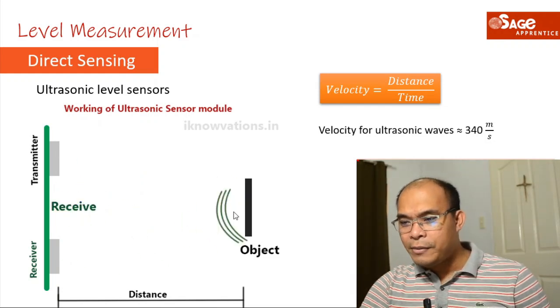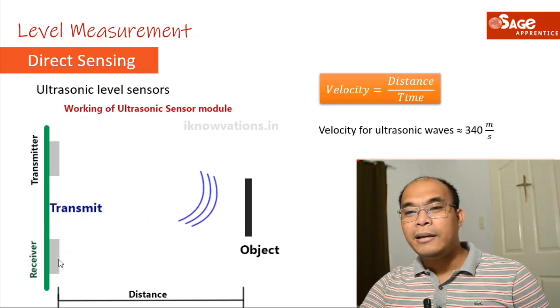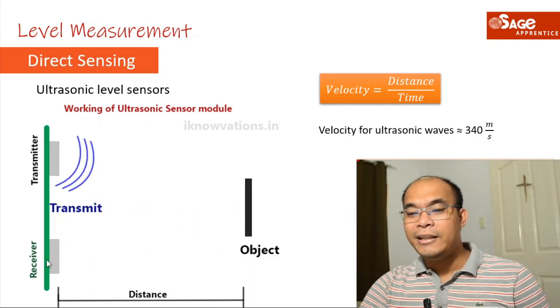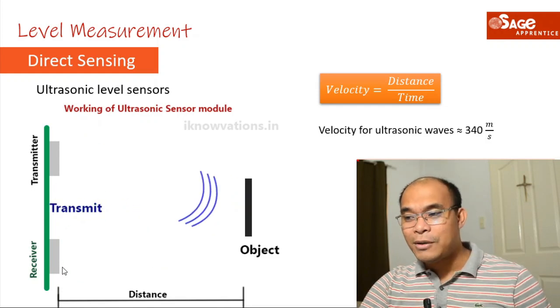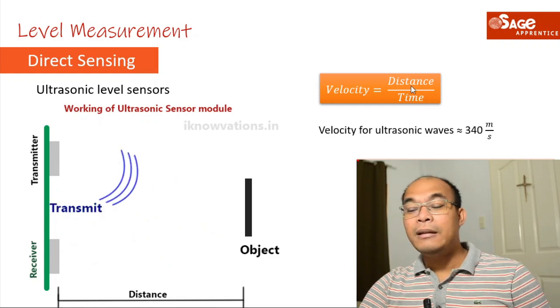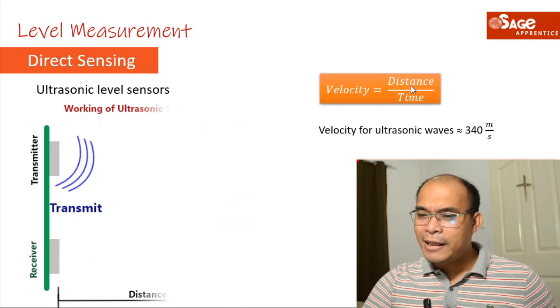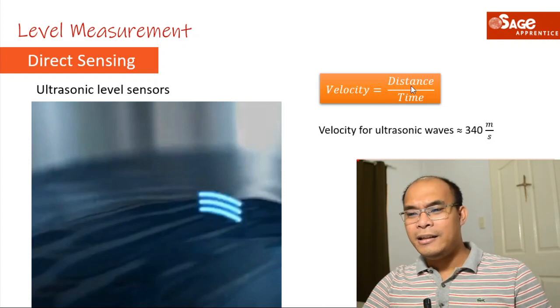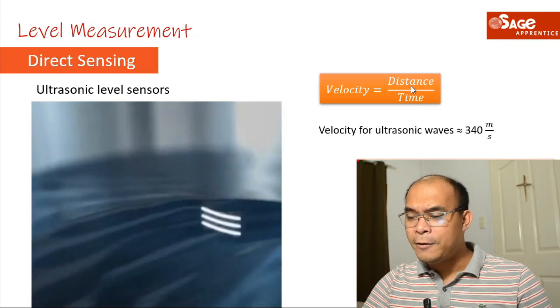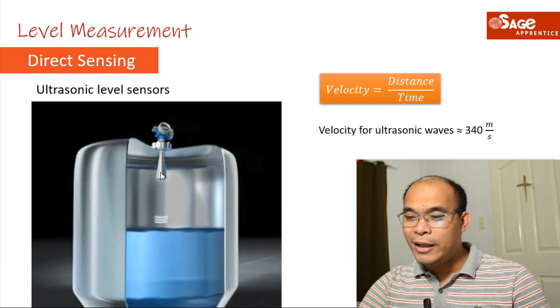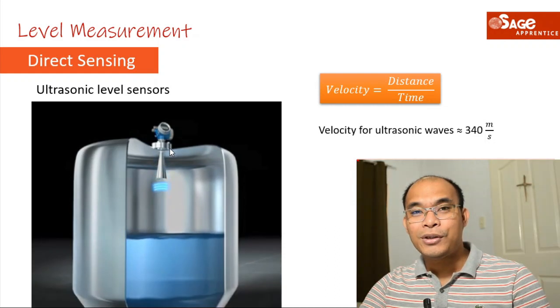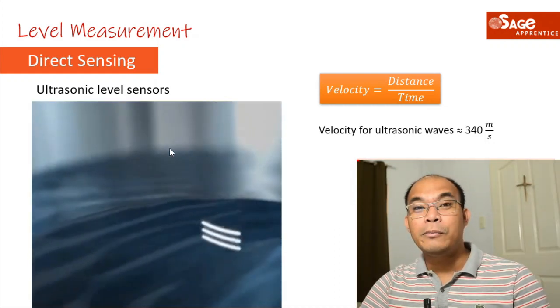You start a timer when the signal is sent and measure the time it takes to travel from the transmitter to the object and back to the receiver. From the known velocity and measured time, we can solve for the distance. For example, the ultrasonic sensor transmits a signal, the echo reflects, and the receiver picks it up. This is how ultrasonic level sensors measure level, especially in closed tanks.